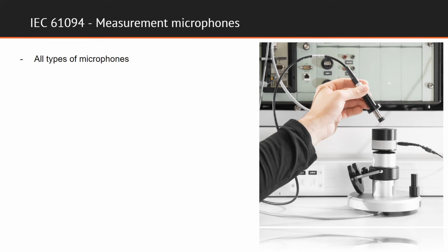In addition to the before mentioned calibration of the complete measurement chain, which would include microphone, cables, data acquisition unit, and software, meaning the SLM plugin, all of which can be calibrated as Class 1 SLM, separate calibration of the measurement microphone alone is often presumed. Calibration of all types of microphones is performed according to IEC 61094, with or without amplifiers.